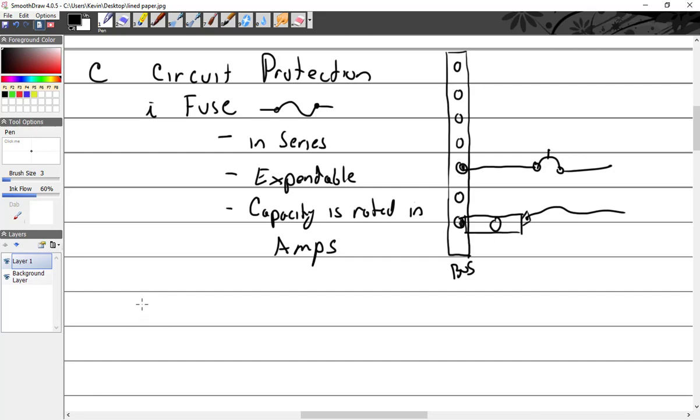Okay, so we got that. Current limiters. I mentioned that. Well, they're like a wire that blows, basically. I wrote this, I'm not going to write it all. A current limiter such as used in the armature circuit of a high current DC generator is a form of a slow blow fuse that will accept a surge of current greater than the generator rating. But if there is a continual flow of current in excess of the generator rating, it will open the armature circuit and remove the generator from the system.